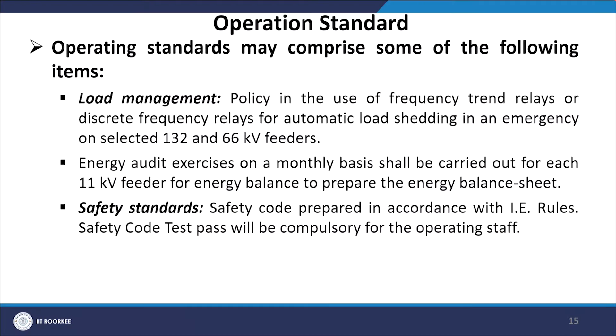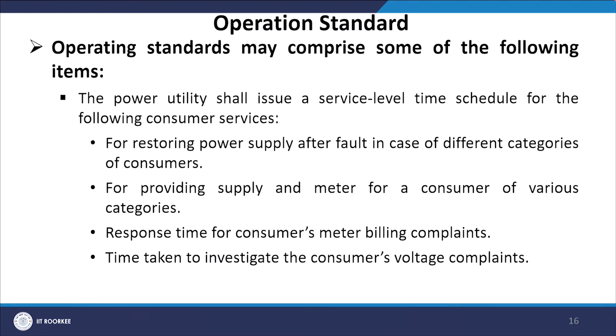For load management, frequency trend relays or discrete frequency relays are used for automatic load shedding under emergency conditions on selected 132 or 66 kV feeders. An energy audit on a monthly basis shall be carried out for each 11 kV feeder to prepare the energy balance sheet. The safety code prepared in accordance with IE rules is mandatory, and safety code test passes are compulsory for all staff. The power utility shall use a service level time schedule for consumer services including fault restoration, new supply connections, billing complaint response, and voltage complaint investigations.